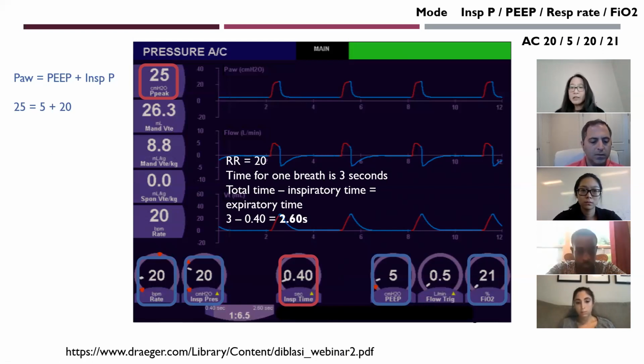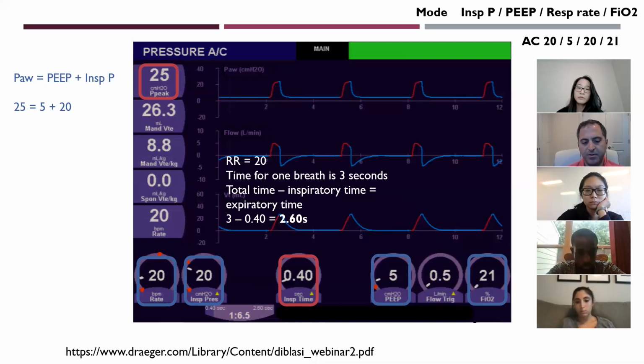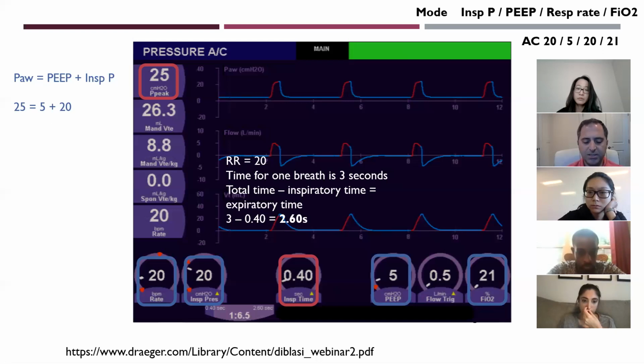Okay, so this is from a Draeger machine. As you said, at the bottom, it actually points out that you set it to 0.4, and then 2.6, based on the respiratory rate of 20, would be your expiratory time. In some machines like Avea, you only set the I to E ratio. So another way of saying all these things is to say, what is the I to E ratio? In this particular patient, the inspiratory time is 0.4 and expiratory time is 2.6. So the I to E ratio would be 0.4 divided by 2.6.